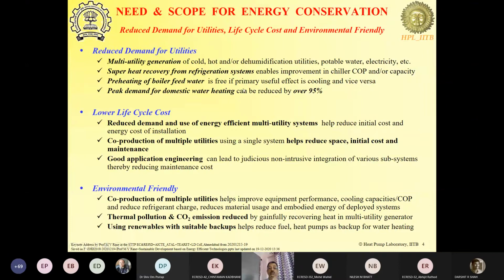Then preheating of boiler feed water can be considered a free utility if cooling is the primary thing, or it can be looked at vice versa: your boiler feed water is the primary utility and cooling is the bonus utility. Then peak demand for domestic water heating can be reduced by over 95%. If you're using electric water heaters, most of them might operate during the morning rush time or the evening time, depending upon the usage and the local culture. All that instantaneous load because of the water heaters can peak up the total demand for the utility.